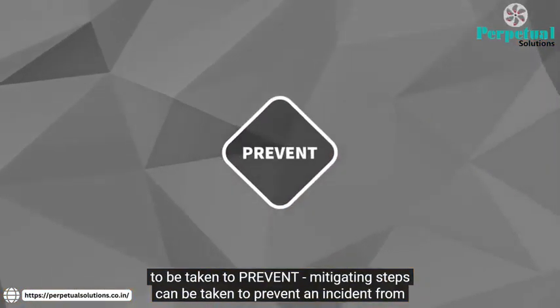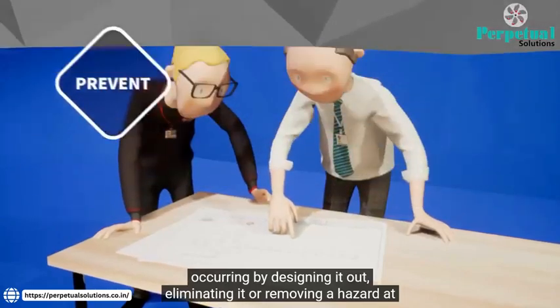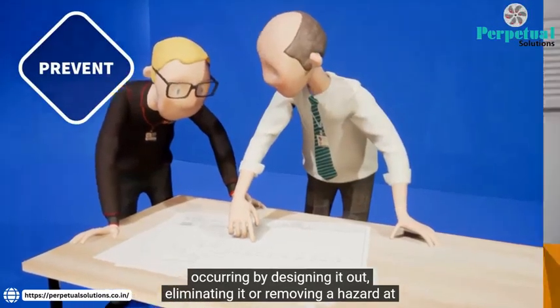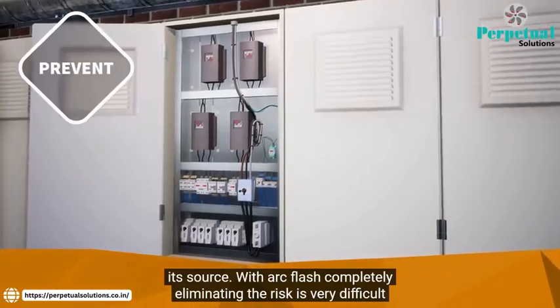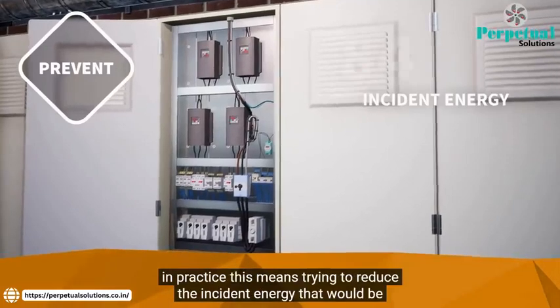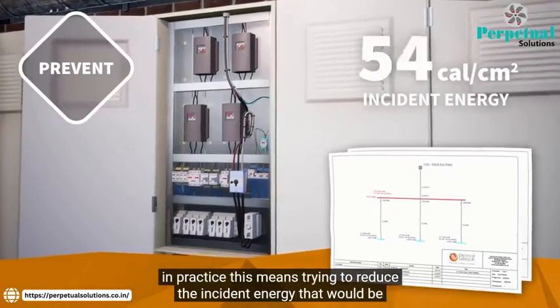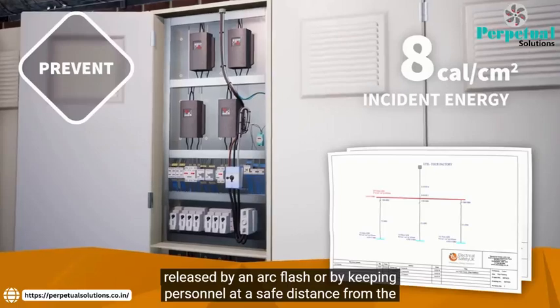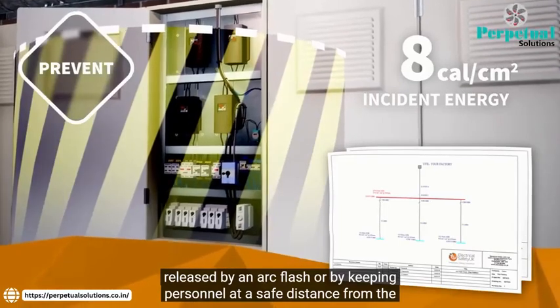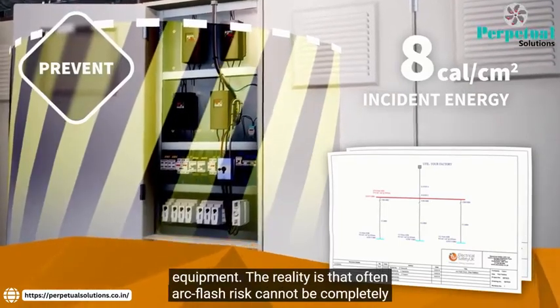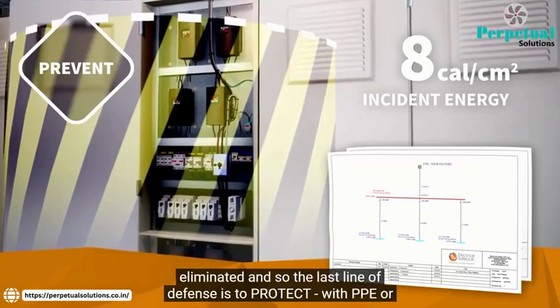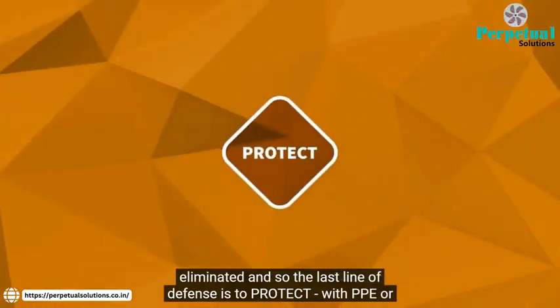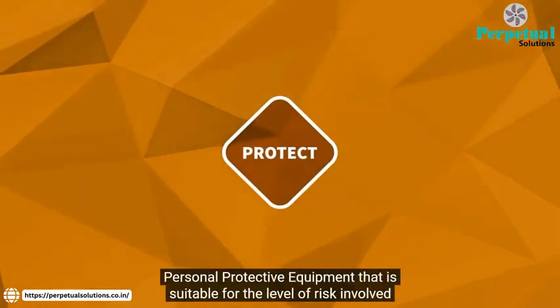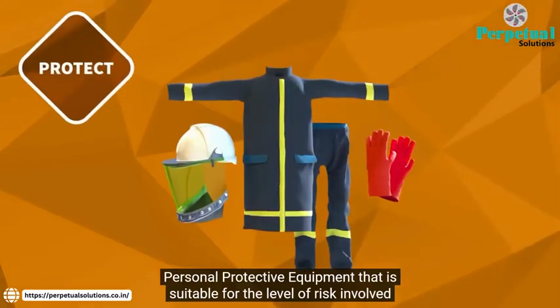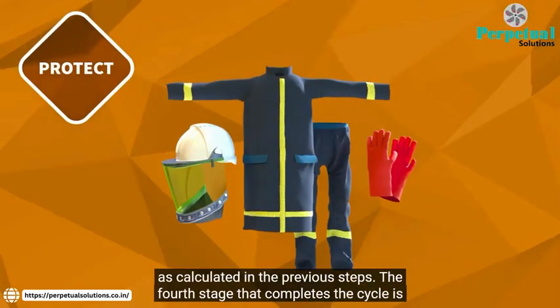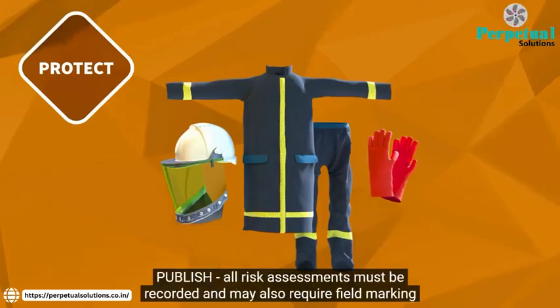Mitigating steps can be taken to prevent an incident from occurring by designing it out, eliminating it, or removing a hazard at its source. With arc flash, completely eliminating the risk is very difficult. In practice, this means trying to reduce the incident energy that would be released by an arc flash, or by keeping personnel at a safe distance from the equipment. The reality is that often arc flash risk cannot be completely eliminated, and so the last line of defense is to protect with PPE, or personal protective equipment, that is suitable for the level of risk involved as calculated in the previous steps. The fourth stage that completes the cycle is publish.